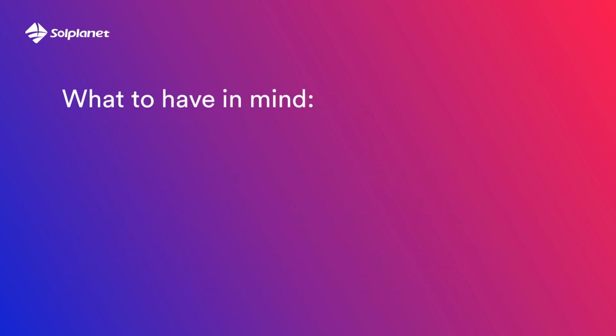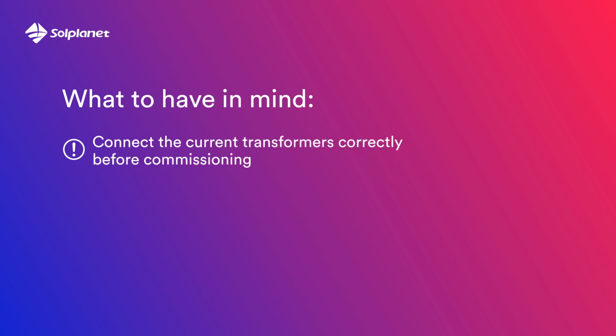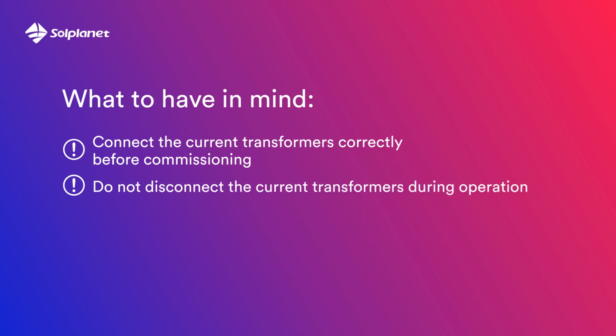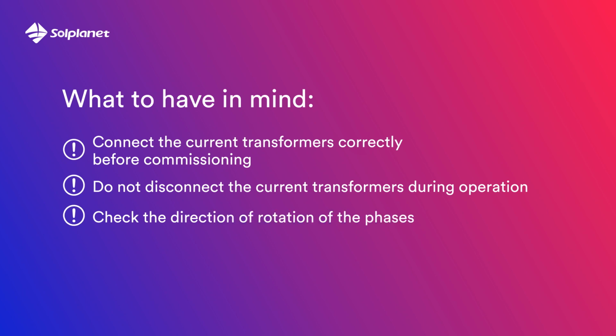Things to remember. Before commissioning, the current transformers must be correctly connected. Do not disconnect the current transformers during operation. Check the phase rotation direction. Update the firmware of the inverter and Wi-Fi module.